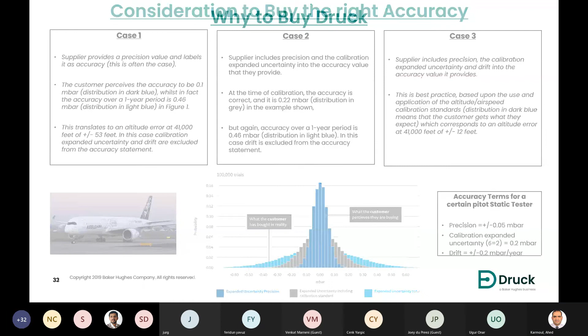Case number 3: if the supplier includes the precision, calibration expanded uncertainty, and drift in the accuracy value, this is the best practice. He will give you the idea that this is the maximum error that can happen, and this is the worst case scenario over a period of time, which is 1 year, 15 months, or 18 months. If you remember when we spoke about the products, we said these are the specs guaranteed for 15 months or 18 months. And this is what we use in Druck.